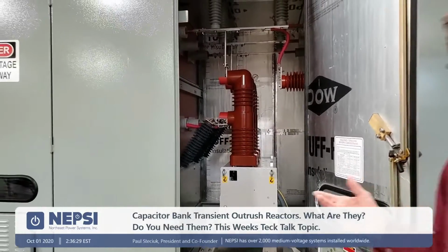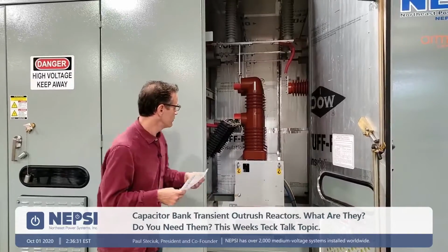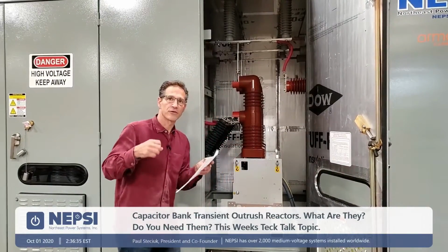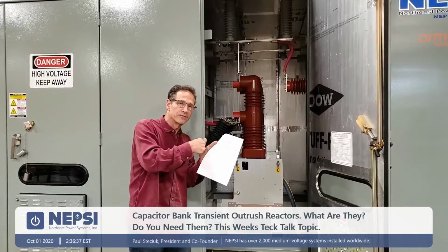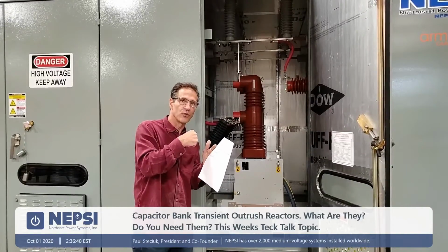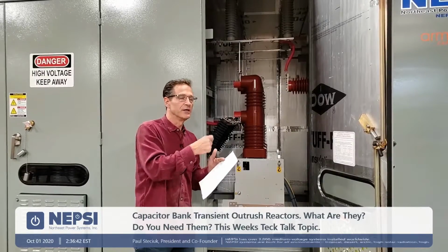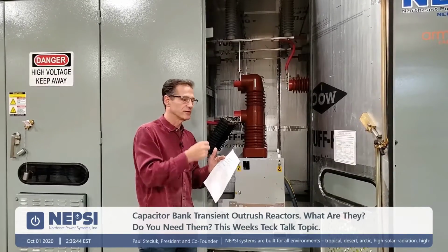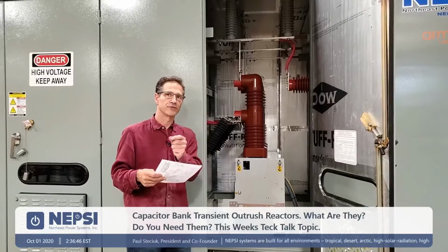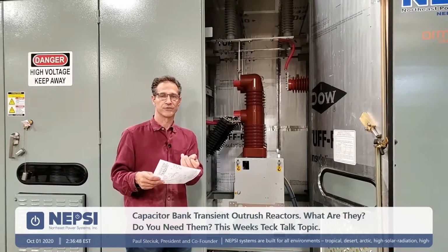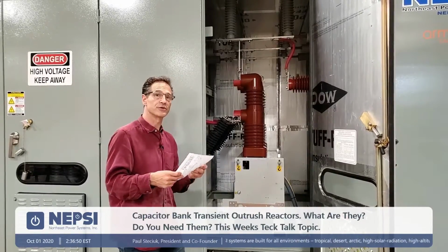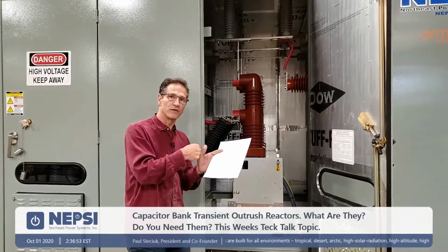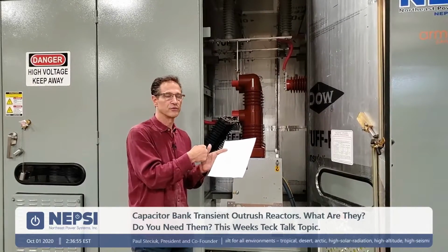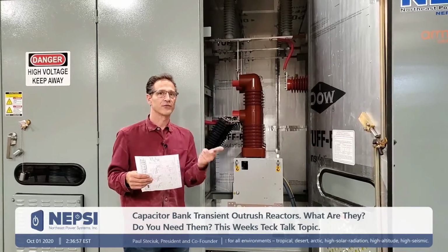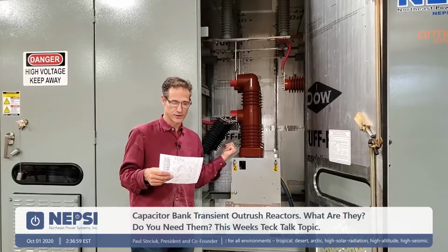It's a significant amount of capacitive current. It uses servo motors within this device here to accelerate and decelerate the contacts so that you get the precise point-on wave closing. Okay, this is a relatively new device. It's an alternate to the Southern States cap switcher, which uses pre-insertion resistor technology. So this is using point-on wave, looking to basically close on zero voltage. We have recorded several videos on this technology, so we won't get into it too much.